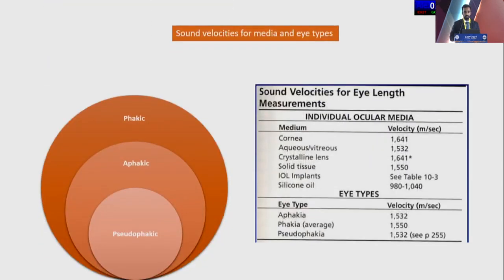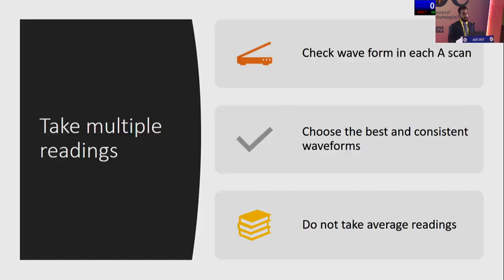These are the sound velocities that have to be modified for different cases. For aphakia, make sure that you are selecting the aphakia mode, and for silicone oil, do select silicone oil mode. Another important thing when you're doing an immersion biometric scan is to select the immersion mode on the biometer, and also take multiple readings, and for every reading check the waveform in every A-scan. Choose the best and the most consistent one. Do not take an average of all the readings. If you're taking 5 readings and 2 readings are way out of bounds, it will be better to eliminate those 2 readings and take an average of the 3 readings which are all similar to each other with the same axial length.